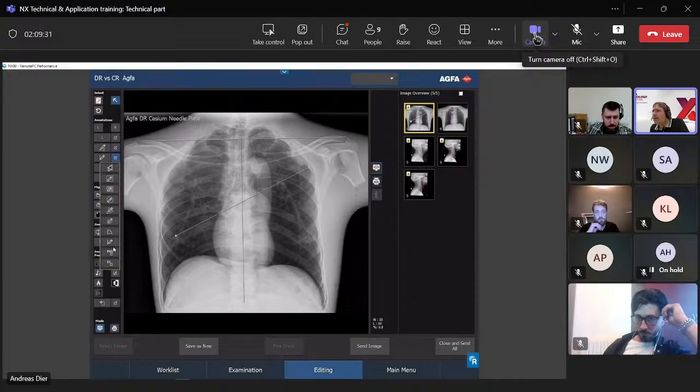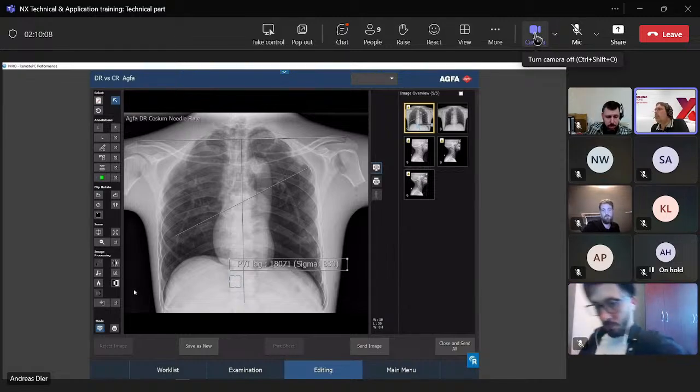That's easy. And here these two tools, PVI and EI. Here we can measure in the image the pixel value. This is the PVI tool, and the EI value which results from that. So if I click on it, I get this square. I can move it, and I get the appropriate mean PVI log value. So in a darker area, it is of course a bit higher. You see, like this, and if I go here, then the value becomes lower.